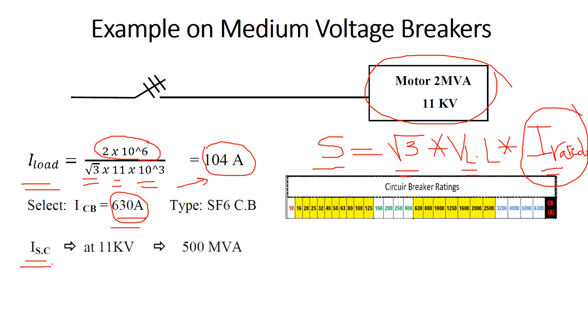Next, we need to find the short circuit current in order to identify the required breaking capacity — the maximum short circuit current our circuit breaker must withstand. From the previous data, the 11 kV grid has a short circuit power of 500 MVA.